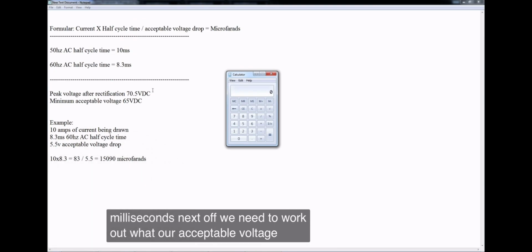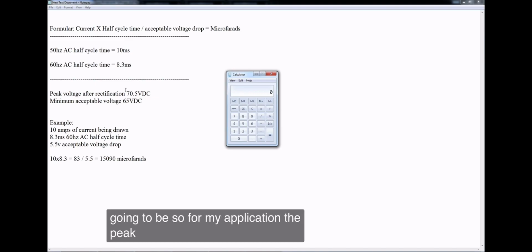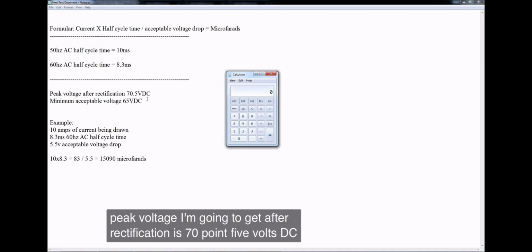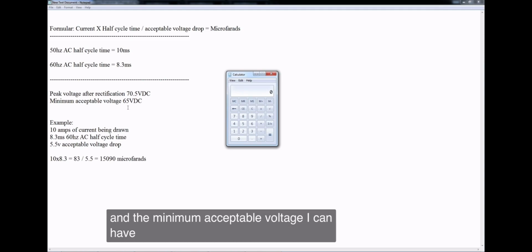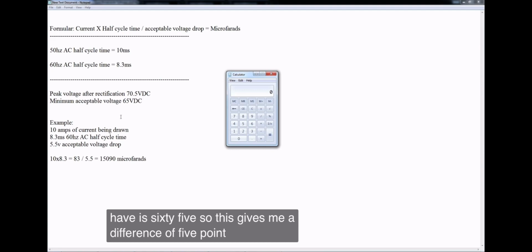Next, we need to work out what our acceptable voltage drop is going to be. For my application, the peak voltage I'm going to get after rectification is 70.5 volts DC, and the minimum acceptable voltage I can have is 65, so this gives me a difference of 5.5 volts DC. So let's break this down. Let's use this as an example.